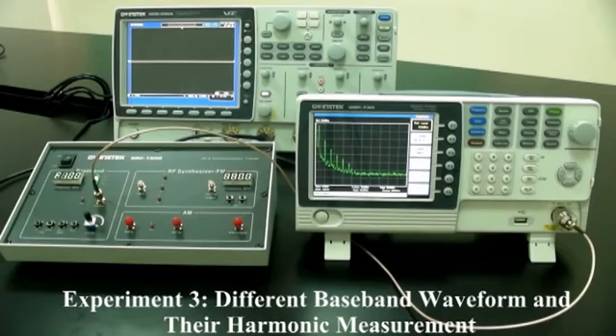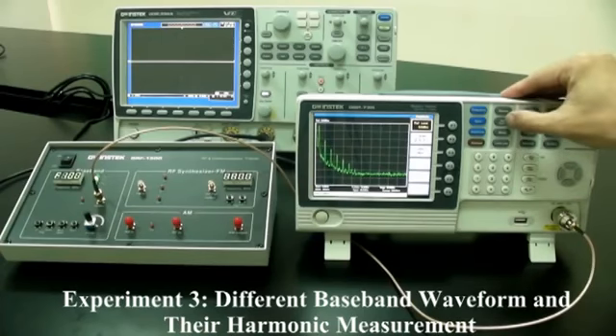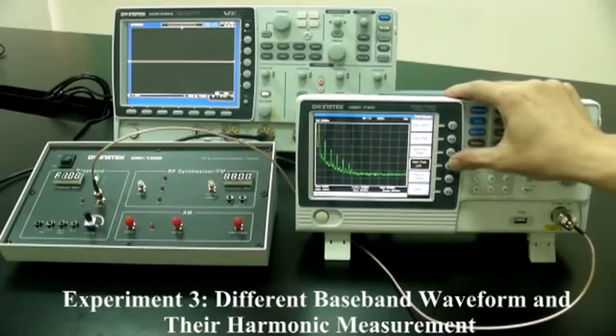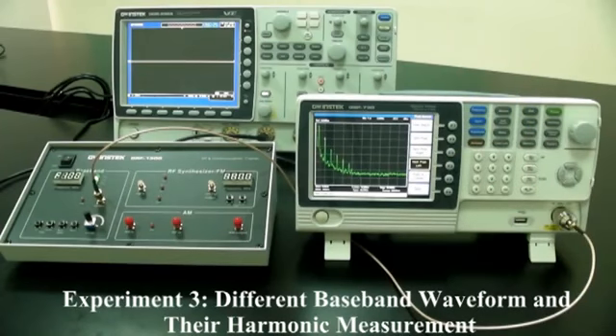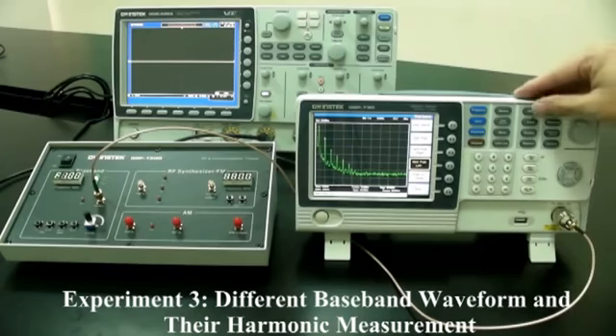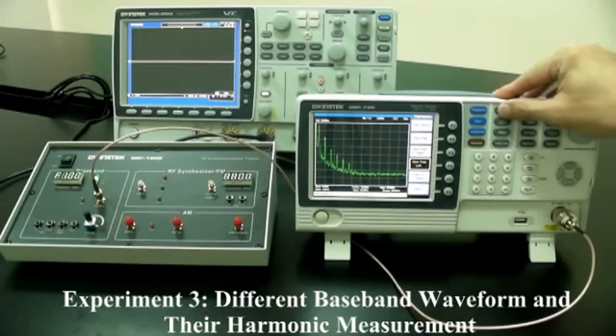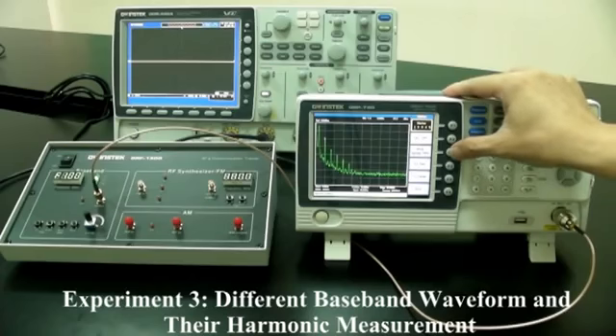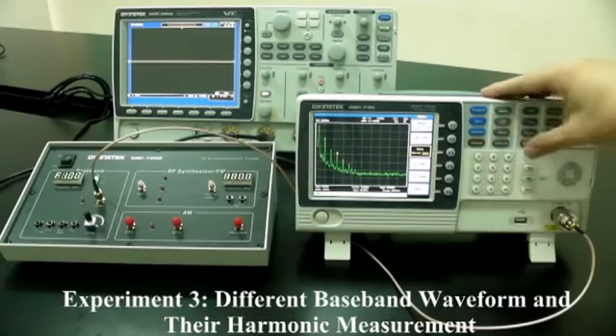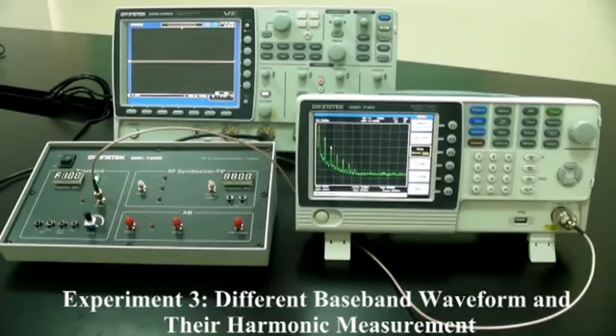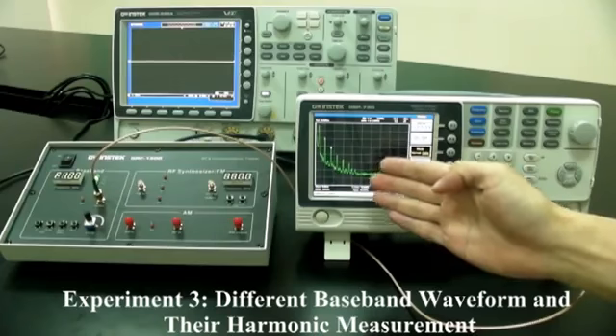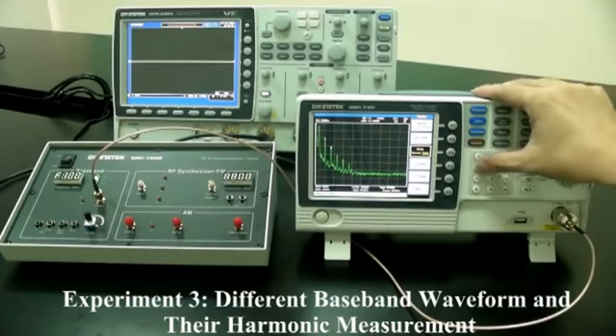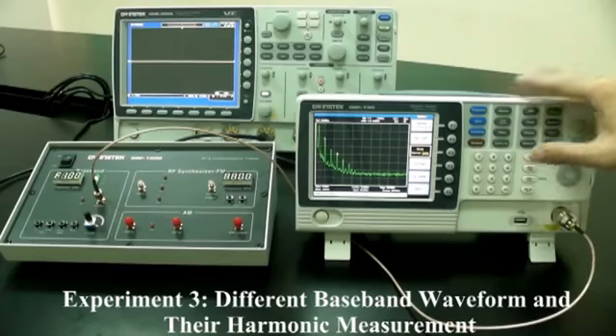Use the marker function on the spectrum analyzer to determine the harmonic ratio. Marker. Mode. Delta. Enter 2 MHz. Now, the second harmonic is shown on the screen. Enter 4 MHz. The third harmonic is shown on the screen.